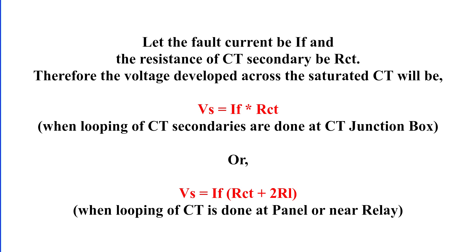If the fault current is IF and the resistance of the CT secondary winding is RCT, then the voltage developed across the saturated CT is Vs equals IF multiplied by RCT when paralleling is done at CT junction box. Or if paralleling is done at the relay panel or near the relay end, we must also consider the lead resistance RL giving us Vs equals IF multiplied by the sum of RCT and two times RL.